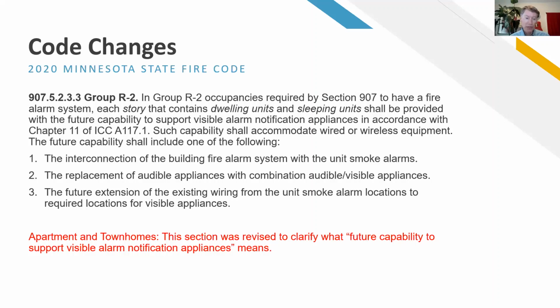I want to give a bonus tip for all of you that manage buildings: when do you need visual signaling, and when do you need audio signaling? The common sense behind the code is if I get a job in an office and I can't hear just because of how I was born, I'm going to let HR know, and HR is going to contact the fire alarm contractor. They'll put a strobe in my private office because I wouldn't be able to hear the speaker strobes out in the corridor in the general area. But if I go to a bathroom, a conference room, a wellness room, mothers and nursing rooms, etc., you need to make sure that person has a way to understand the fire alarm is going off through visual signaling. That's a bonus tip behind some of the fire codes.